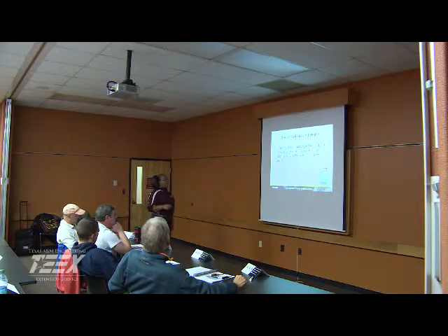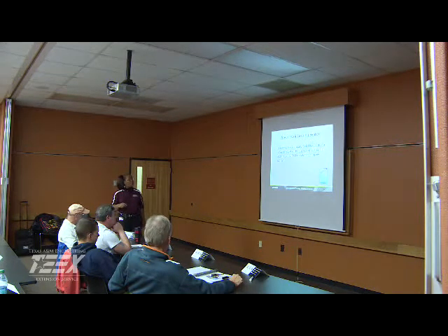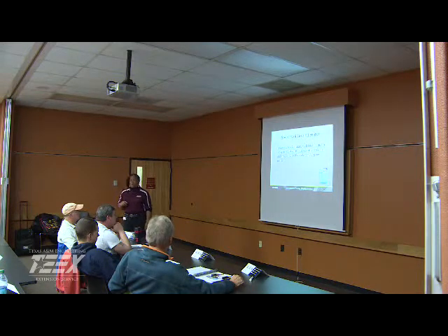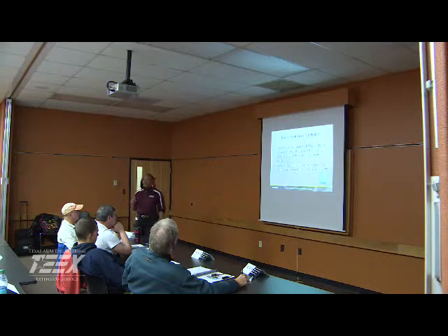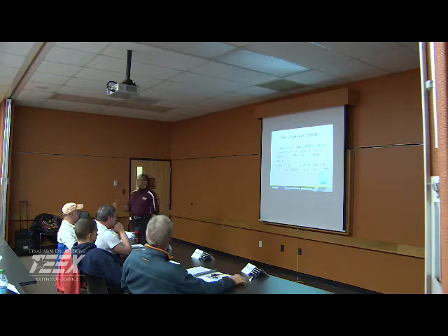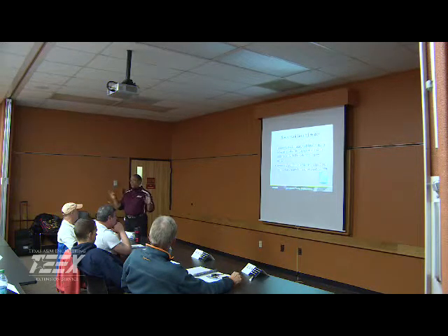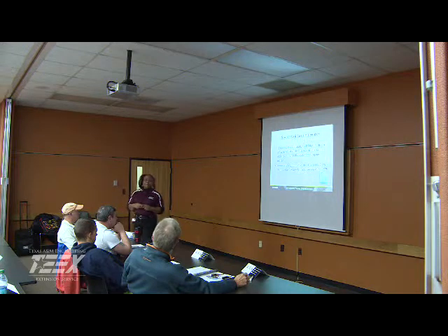So, groundwater is usually well filtered, as we said before, due to the layers of soil and slow percolation through the earth material. Usually there is very, very little turbidity, which is a major problem with surface sources, and there should be little color as well as organic matter. However, because of the rocks, soil, and mineral content, and because water is the universal solvent, as it percolates down over those media, anything that's in that rock can be dissolved into the water. So generally groundwater is higher in dissolved minerals or total dissolved solids, more so than surface water from the same area.